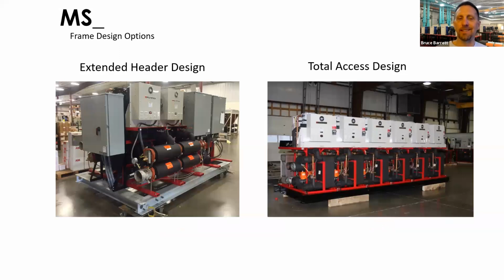We do have extended header offerings. We do these a lot when we're starting to compile a pre-mounted skid. The piping's a little further apart. It's a little easier for us to work with. On here, we've got pumps on the right-hand side of the palletized, or we call it a lifting frame. The drives are in the gray panels on the right-hand side. And we ship this as a pre-engineered product, right down to gauges, temperature sensors, whatever's required or requested by the customer.